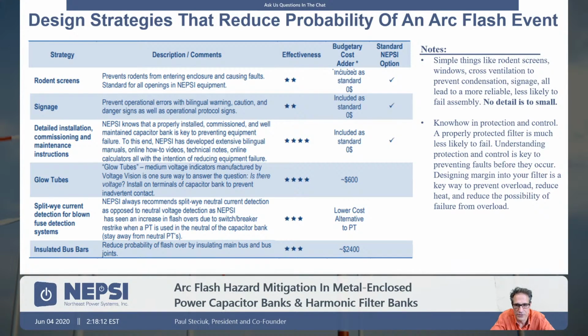If you have signage that tells you how to operate the equipment, what to watch out for as you step along during the operation of the equipment, you're less likely to make a mistake. It is mistakes that lead to arc flash hazards. We have a very detailed installation, commissioning, and instruction manual. You need to have details. You need to understand how the equipment works.